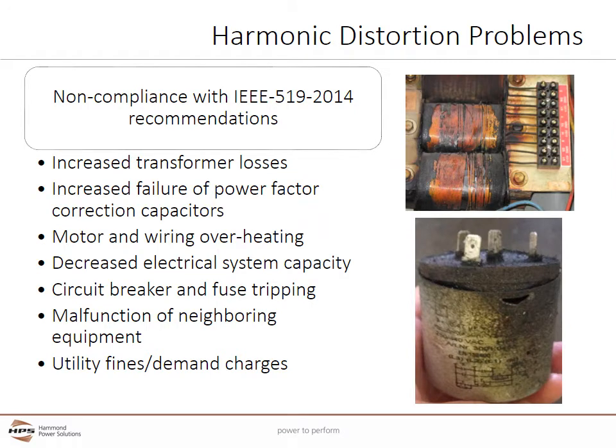IEEE 519, of which the most current version is 2014, is a document that establishes levels of voltage and current harmonic distortion acceptable to the distribution system, based on the input transformer characteristics and the loads in a customer's facility. Many electrical consultants are including compliance with IEEE 519-2014 in their design specifications to help reduce harmonic problems and avoid penalties that can be imposed by electrical utilities. More information about the levels of harmonics can be found on the IEEE website.